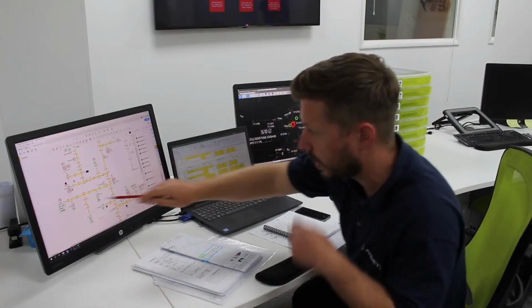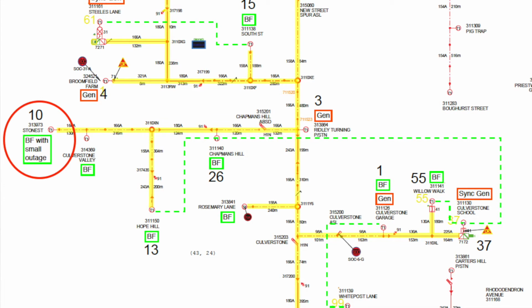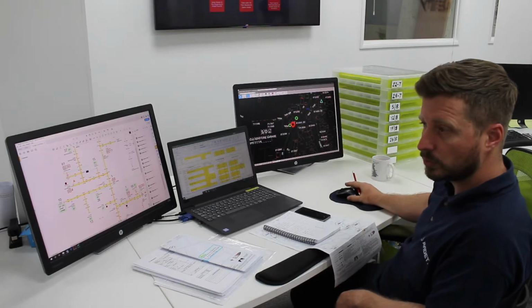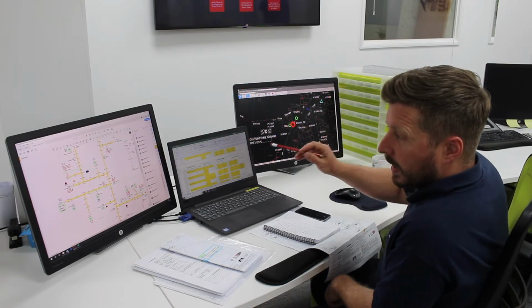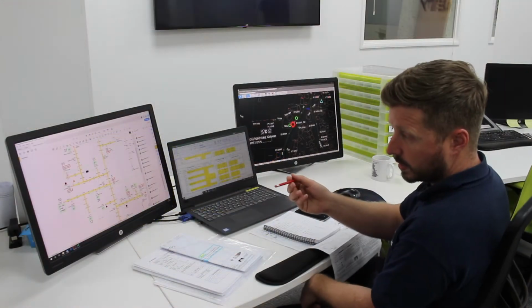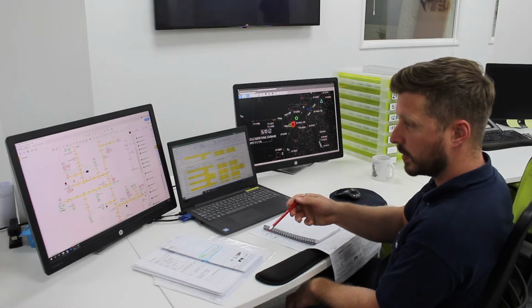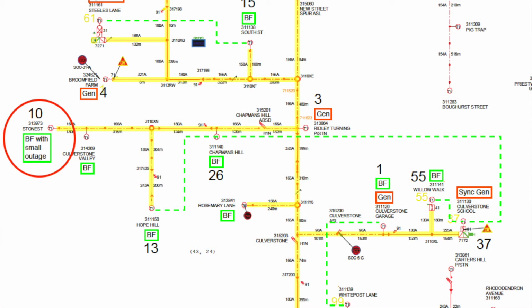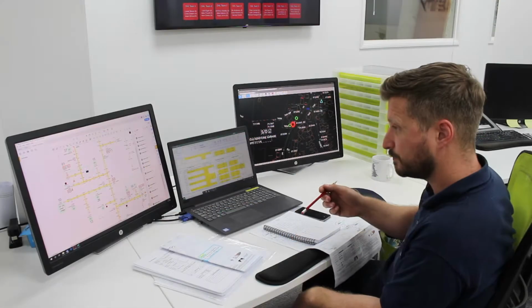Now, if we come down here to Stonest, it's a single phase transformer that is back feedable, but it's via another single phase transformer that it doesn't phase in with. So it would have been pretty easy to just connect a generator on that one. But the backfeeding transformer is perfectly capable of handling the capacity there. So where we would usually have a 45-minute interruption to connect a generator, we're going to just allow half an hour to remove the fuses at Stonest and apply the backfeed from the other end. So we've got 10 customers for 45 minutes, 450 customer minutes, and we're dropping that down to 300 customer minutes, so 150. But we're also losing the potential inconvenience of having a generator and the additional cost as well.